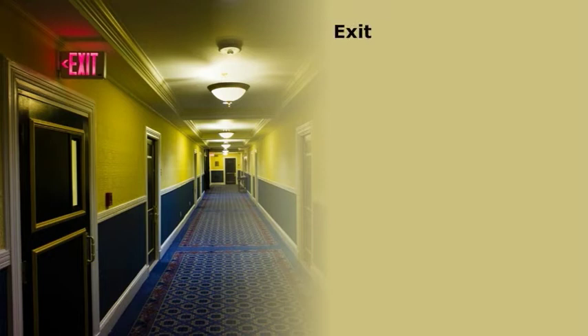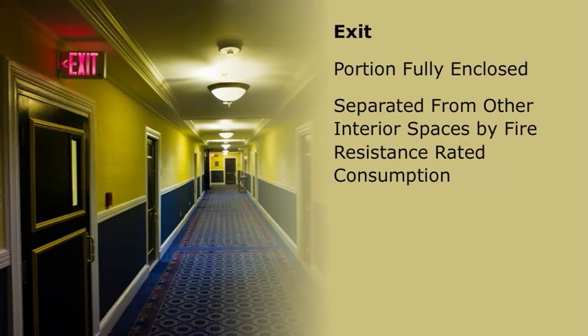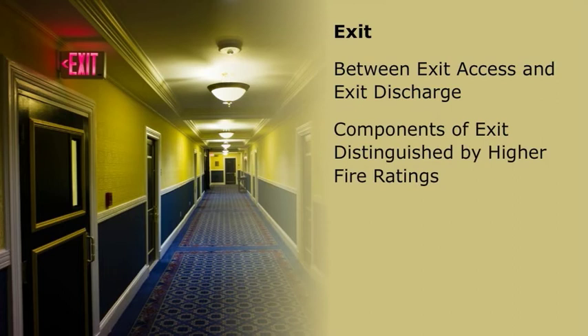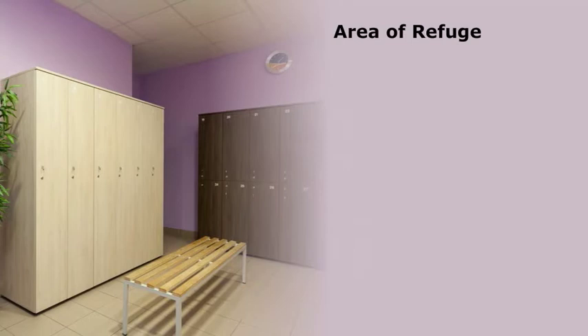The second component of a means of egress is the exit. The exit is the portion of a means of egress that is fully enclosed and separated from other interior spaces by fire-resistance rated construction, and is between the exit access and the exit discharge or public way. It can be as basic as the exterior exit door, or it can include enclosed stairwells and ramps. In some special cases, it can include certain corridors or passageways. The components of an exit are distinguished from the exit access by higher fire ratings.